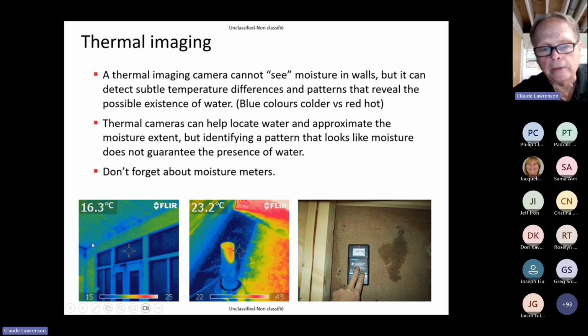And if we take a look along this beam here, which is just on the inside before we get to the outside, we can see some blue also developing here. So again, moisture buildup in this particular, we'll call it ceiling space. This is a roof, and this is a vent pipe, a plumber's vent pipe. We can see colors from blue, moisture problems, water problems, to the heated area over here, getting into the yellows, oranges, and reds. So again, potential moisture buildup.